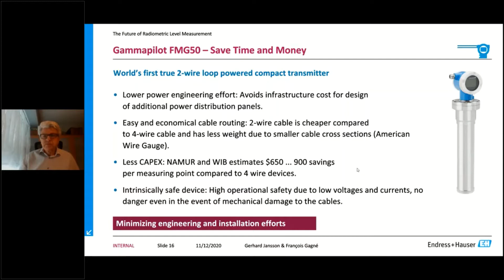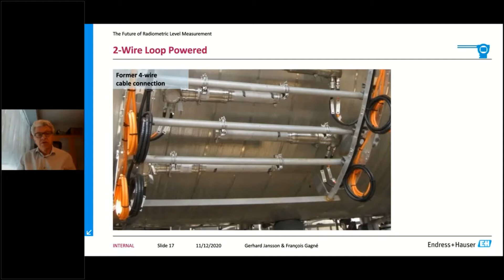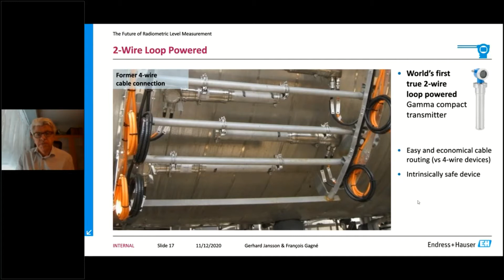So if you look at this picture, we can see the reduced effort, because with a 4-wire device you have a power supply and the 4-20 milliampere communication to each of those devices. If I now have a loop-powered instrument, I would only need one pair of these cables, so there will be a reduction in wiring costs. This can be general purpose, intrinsically safe, as they say here, as well as explosion-proof devices.